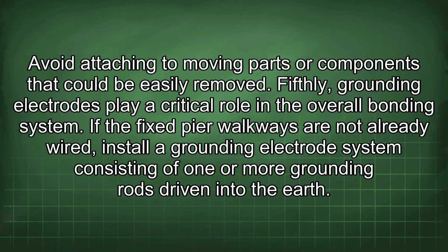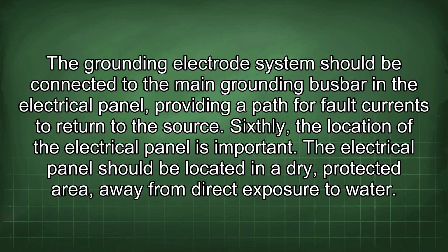Fifthly, grounding electrodes play a critical role in the overall bonding system. If the fixed pier walkways are not already wired, install a grounding electrode system consisting of one or more grounding rods driven into the earth. The grounding electrode system should be connected to the main grounding busbar in the electrical panel, providing a path for fault currents to return to the source.